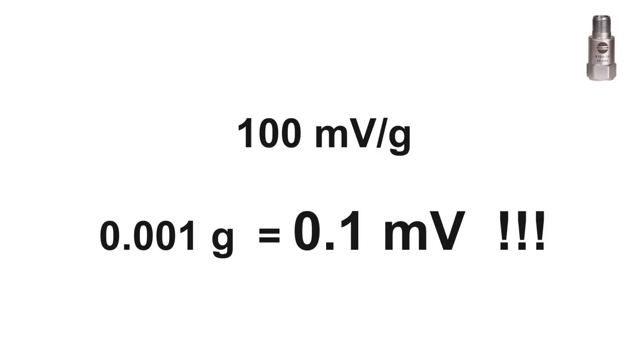If the sensor sensitivity is 100 mV per g, then the voltage for 0.001 g is 0.1 mV. It is not too much. Can you measure such voltage level? The answer is no.